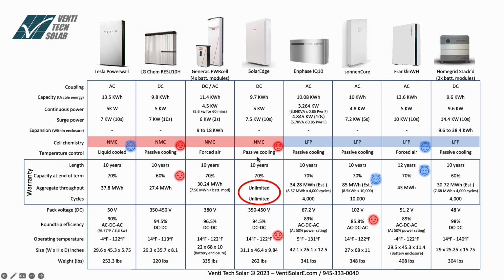But since it is passive cooling and it is using NMC batteries and they're pushing the envelope of what the operating temperature is, I would expect that a lot of these modules are going to fail. In my opinion, it looks like they will nickel and dime, they will find ways to invalidate the warranty. It looks like it's a way to get market share in comparison with the rest of the vendors. It's a marketing strategy more so than a real warranty, because there will be people that will push these cycles. They will run more than 4,000 cycles or they will get multiple cycles a day. So these batteries are going to fail in 10 years, or they will have less than 70% of their life expectancy at the end of 10 years. So in my opinion, this is a bad warranty. So for that, I'm giving it a frowny face.